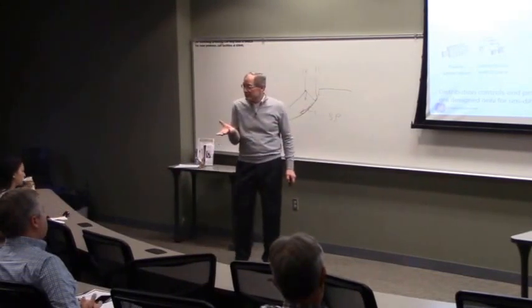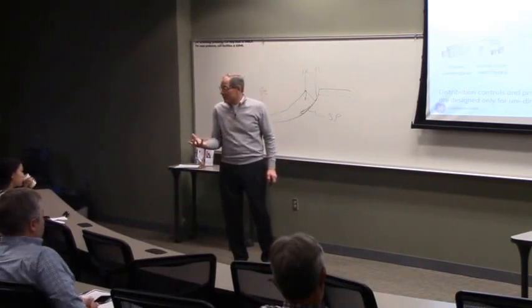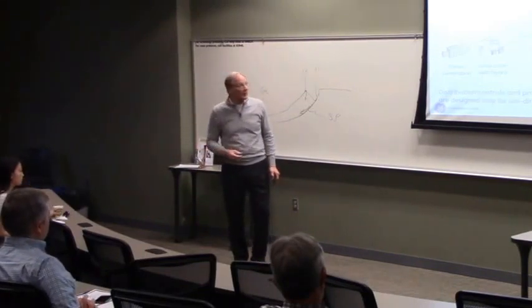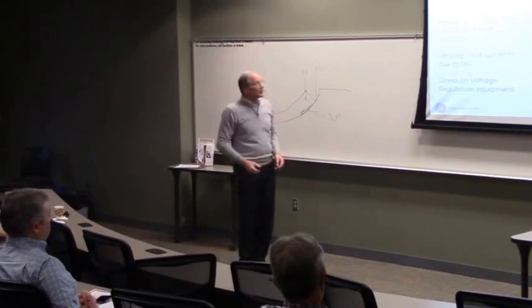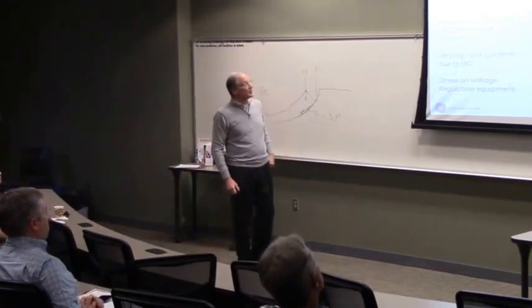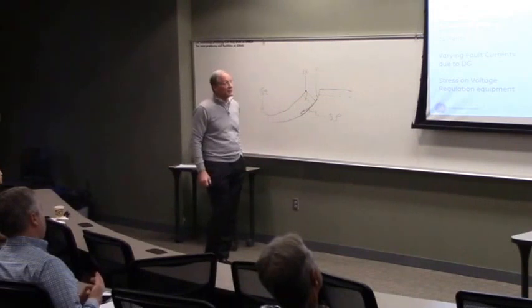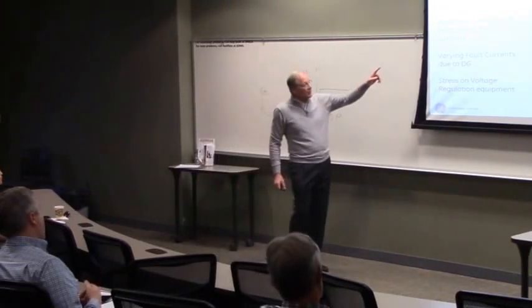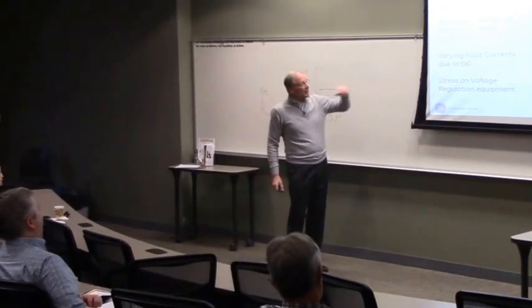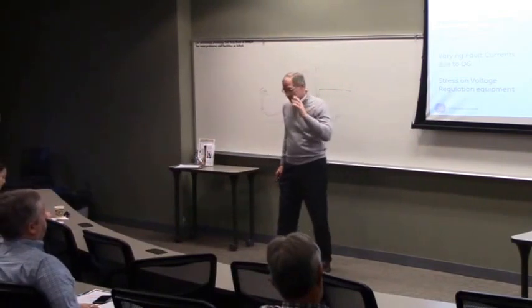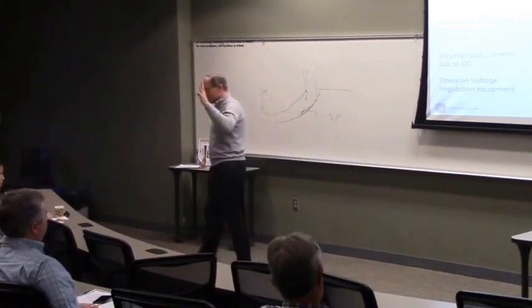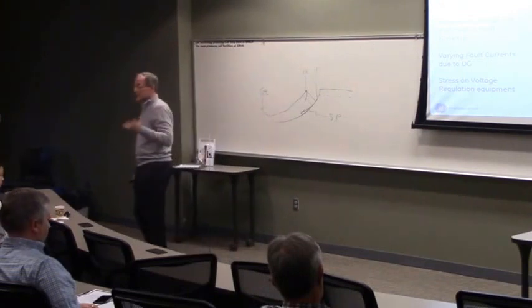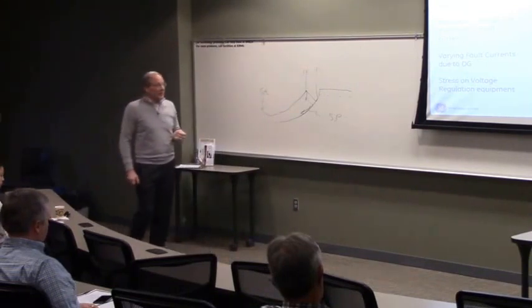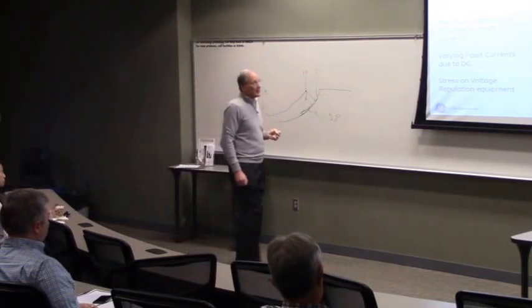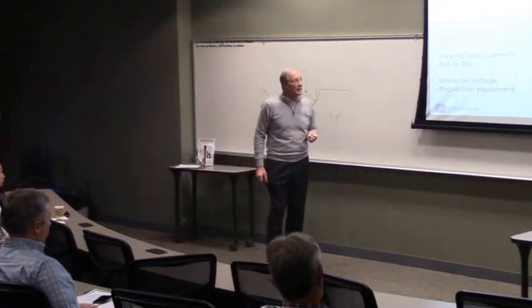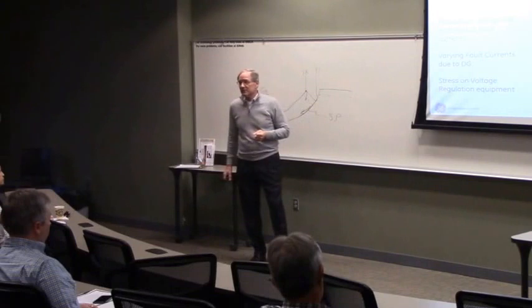We put distributed generators on the feeder. Now we have load side contribution if there's a fault. Okay. We also have open circuit overvoltage possible due to unintentional islanding. When a fault occurs, the fault currents that we get, in our short circuit study we looked at source side contribution only. Now we have a load side contribution. So the protection ratings may not be the right settings based on the fault currents.